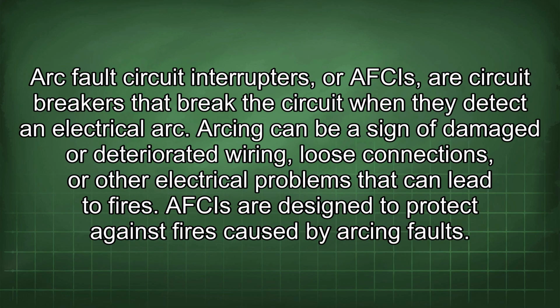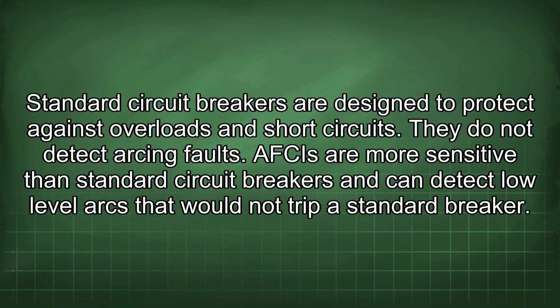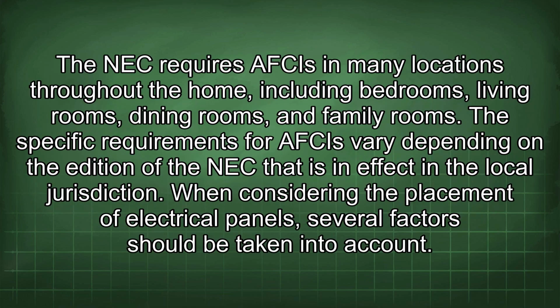Arc fault circuit interrupters, or AFCIs, are circuit breakers that break the circuit when they detect an electrical arc. Arcing can be a sign of damaged or deteriorated wiring, loose connections, or other electrical problems that can lead to fires. AFCIs are designed to protect against fires caused by arcing faults. Standard circuit breakers are designed to protect against overloads and short circuits. They do not detect arcing faults. AFCIs are more sensitive than standard circuit breakers and can detect low-level arcs that would not trip the standard breaker. The NEC requires AFCIs in many locations throughout the home, including bedrooms, living rooms, dining rooms, and family rooms. The specific requirements for AFCIs vary depending on the edition of the NEC that is in effect in the local jurisdiction.